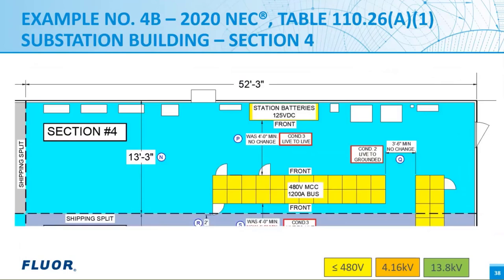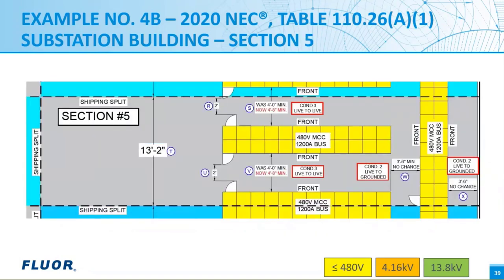Here in section four, it's going to remain unchanged other than what occurred in section one off over there to the left that we looked at a while ago, where we added the 3 inches to comply with the 2020 NEC. Section five is going to grow by 8 inches on each of the two workspaces for a total increase of 16 inches shown near bubbles S as in Sam and V as in Victor. We grow from 4 foot previously to now needing 4 foot 8 inches for each front to front distance based on a 20 inch wide vertical section of motor control center with a 16 inch door. This is another one of those scenarios we spoke about earlier about the equipment rating and the dimensions that you may be able to take advantage of.